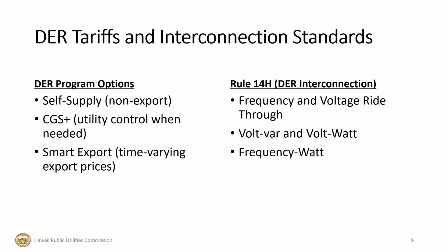So in particular, we've identified that frequency disturbances necessitate wider ride-through settings for PV systems so that they don't trip offline when we have frequency disturbances on our smaller grids. And that was initially the main concern and the highest priority. More recently, advanced inverter functions that help to regulate voltage have been identified as needed, and we've made changes to the standards to require that functionality as well, which has the added benefit of making it easier for everyone to interconnect to the system, because voltage issues can be a constraint for new customers to sign up.